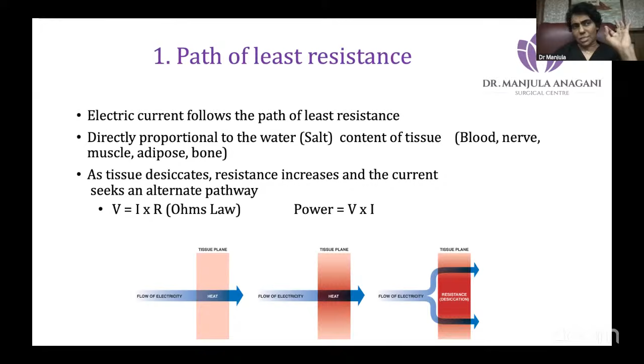Here, you keep hearing so many people saying blend 1, blend 2, blend 3, pure cut, and coagulation. What is important when we talk about this is the waveform: how many times it is silent, how many times it is acting. Once our power is constant, it is the voltage which varies. When you put pure cut, it is on 100% of the time. That means the same amount of electricity goes in during that 100% activity. So voltage is less, so side effects and complications are less.